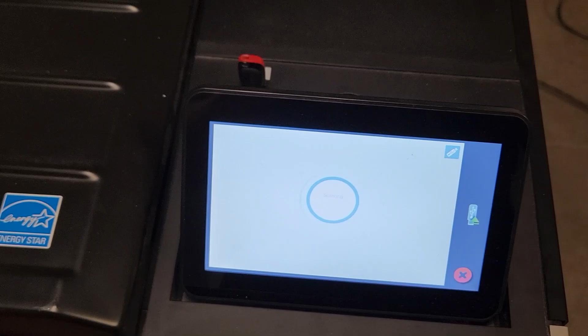input into the system. Once you have your file, go ahead and import it into the system and select Scan Charuco Image. The goal is to scan as many corners as possible. If a few corners are missing, no worries. We can adjust those points in the next step. We can monitor the scan in the top right corner.